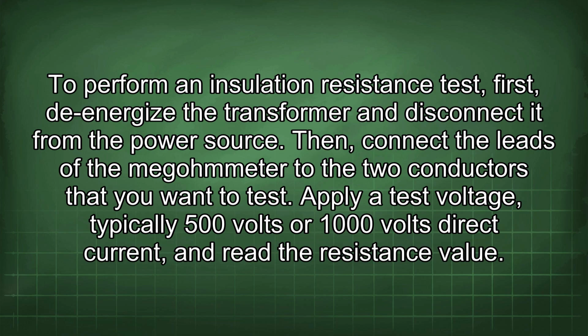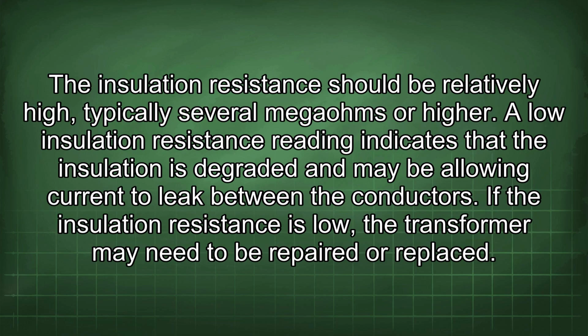Apply a test voltage, typically 500 volts or 1000 volts direct current, and read the resistance value. The insulation resistance should be relatively high, typically several megohms or higher. A low insulation resistance reading indicates that the insulation is degraded and may be allowing current to leak between the conductors. If the insulation resistance is low, the transformer may need to be repaired or replaced.